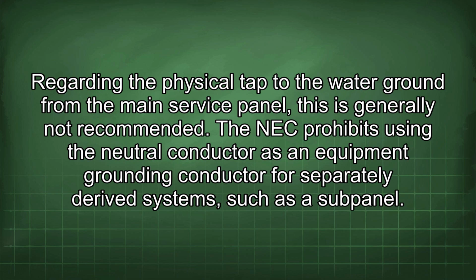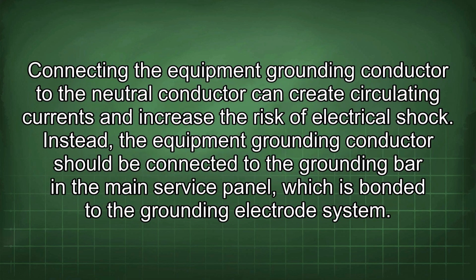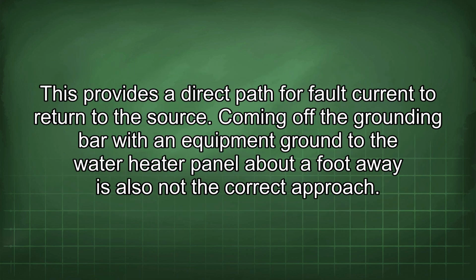Regarding the physical tap to the water ground from the main service panel, this is generally not recommended. The NEC prohibits using the neutral conductor as an equipment grounding conductor for separately derived systems, such as a subpanel. Connecting the equipment grounding conductor to the neutral conductor can create circulating currents and increase the risk of electrical shock. Instead, the equipment grounding conductor should be connected to the grounding bar in the main service panel, which is bonded to the grounding electrode system. This provides a direct path for fault current to return to the source.